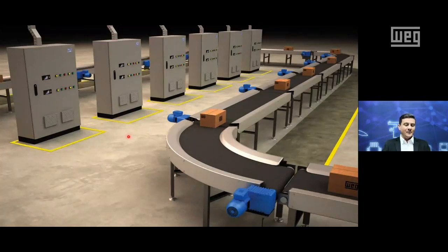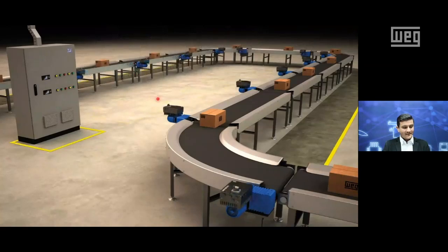Here I brought you an illustration for an easy understanding of the comparison between a centralized and a decentralized solution. In the first picture, as you can see, all the inverters, filters, and other components are fitted and installed inside the control panel, okay? While in this second picture, the VSD is now mounted directly on the motor terminals. So further to all the potential savings that we've already talked about, we can see the possibility to reduce physical space within the installation as well. So this is another potential saving that can be considered when you are using a decentralized variable speed drive concept solution.